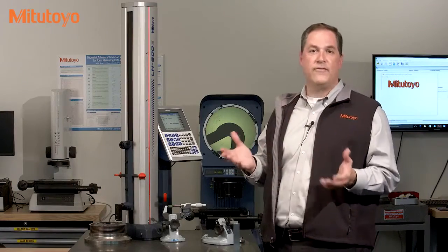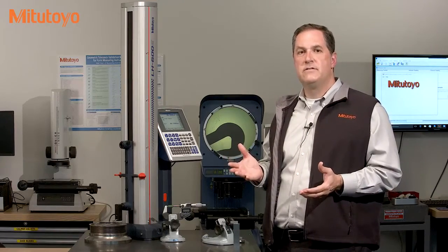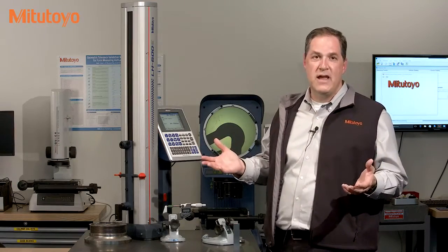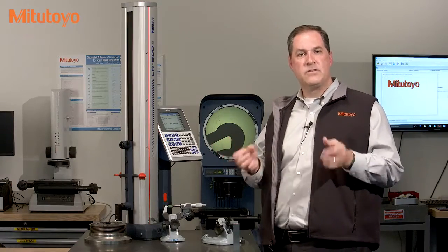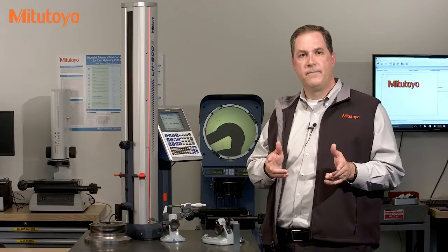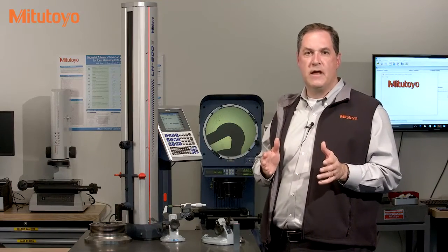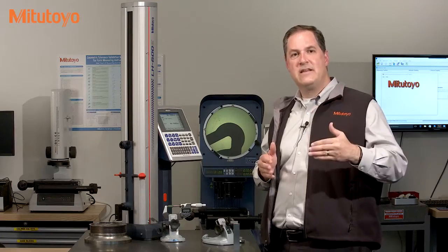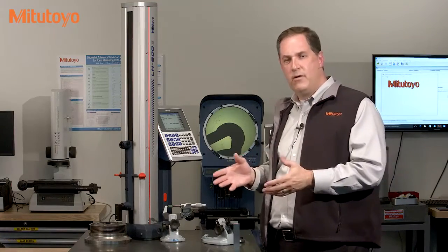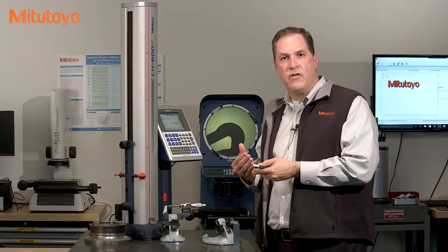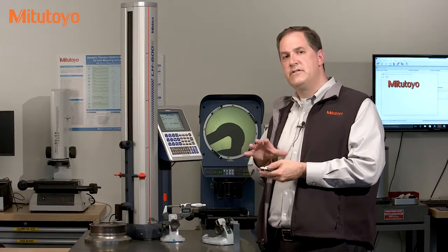But, as we have discussed in prior episodes of the Metrology Training Lab, just saying calibration does not mean you will get all of that. You need to be careful when contracting calibration services. Calibration, verification, manufacturer specifications, adjustments, conformity assessments, you never know what you might get, so specify your needs carefully. One important aspect of calibration that we'll cover in a different episode is the extent of calibration that is needed. For example, how many different tests are needed, or the number of test points required to be considered a sufficient calibration.